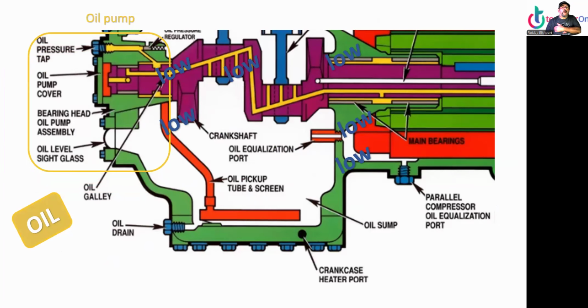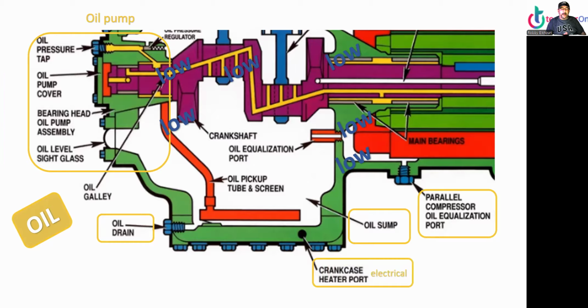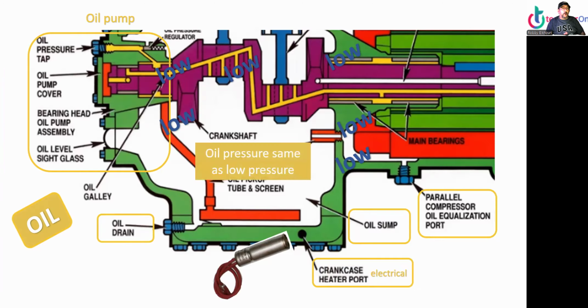Alrighty, now the oil section. Over here, this is the oil pump. We have the oil pressure tap, oil pump cover, the bearing head, oil pump, oil level sight glass. The oil pressure tap, that's how we check the outlet of the oil. I'll cover it later. We have the oil drain and the oil sump. And this is for parallel oil. If you have two compressors in parallel together, you connect the oil together. And last but not least is the crankcase heater, electrical. I covered it in the other slide. Alrighty, oil pressure is the same as the low pressure. And oil pressure tap, the outlet of the oil pressure.